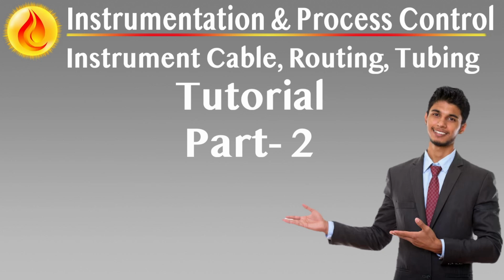Tubing shall enter the junction box through adapter plates fitted with proper strain relief. Where a transition from plastic to copper tubing is required, it must be performed using bulkhead connectors securely mounted on the side walls of the junction box. Angle-type bulkhead fittings are preferred when directional changes are needed, as they reduce stress on tubing and simplify installation. Boxes must provide internal support and clear identification for all terminations to ensure easy troubleshooting and future expansion. Sealing and mounting hardware must be corrosion resistant and compatible with the selected tubing material.